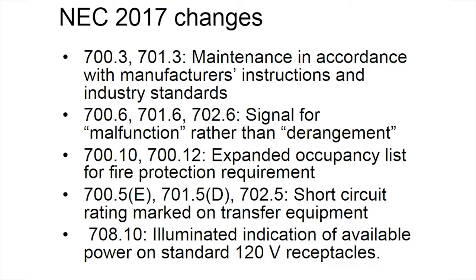And finally, we will look at the changes in the 2017 NEC as regards Article 700, 701, 702, and a brief look at 708. There aren't many, and they don't have a particularly large impact on the installation. 700.3 and 701.3 require maintenance in accordance with the manufacturer's instructions and industry standards. Nothing new about that.